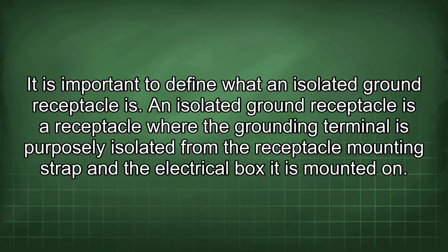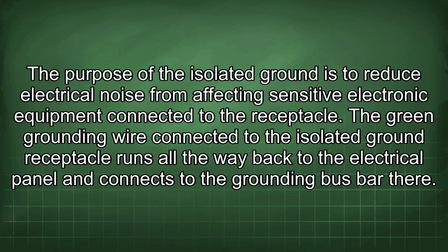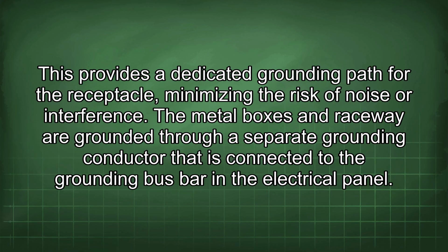250.146(D). It is important to define what an isolated ground receptacle is. An isolated ground receptacle is a receptacle where the grounding terminal is purposely isolated from the receptacle mounting strap and the electrical box it is mounted on. The purpose of the isolated ground is to reduce electrical noise from affecting sensitive electronic equipment connected to the receptacle. The green grounding wire connected to the isolated ground receptacle runs all the way back to the electrical panel and connects to the grounding bus bar there. This provides a dedicated grounding path for the receptacle, minimizing the risk of noise or interference.